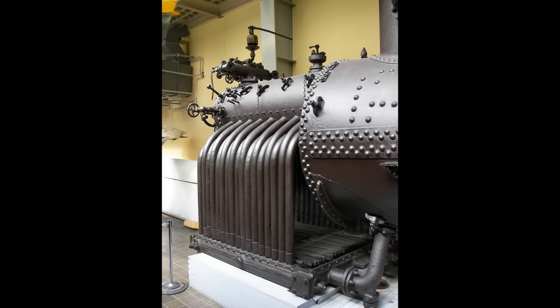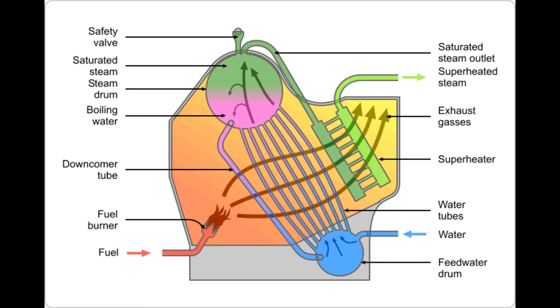As there's a much smaller volume of water being heated, steam is produced a lot quicker and the boiler can respond a lot faster to changes in demand — meaning ships can get up to steam faster and can slow down and speed up more quickly. While running a water tube boiler on impure water can make life very difficult, it does allow you to run the boiler with impure fuels much more easily. The deposits of ash and such tend to build up in areas much easier to clean, and take a lot longer to affect the water tubes themselves or the boiler's operation. They are, however, considerably more expensive.